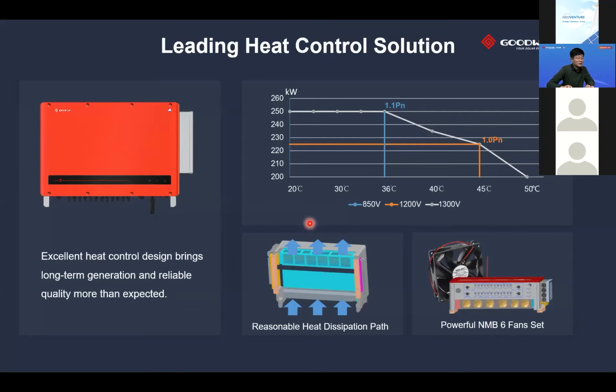And some features. You can see that even in critical situations, like an environment temperature of up to 50 degrees during the product's operation, we can still keep 200 kilowatt output. And if the environment temperature is about 36 degrees, we can achieve 250 kilowatts. We get this great performance because we have a very good design of a reasonable heat dissipation path and very powerful and very safe fans. The excellent heat control design gives the inverters long-term generation and reliable quality.